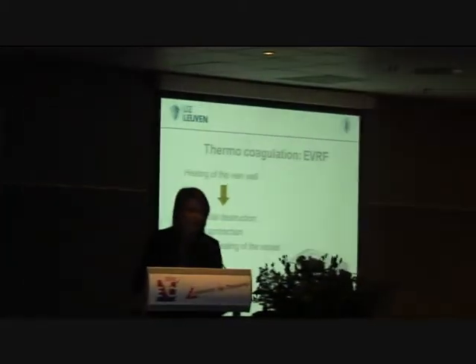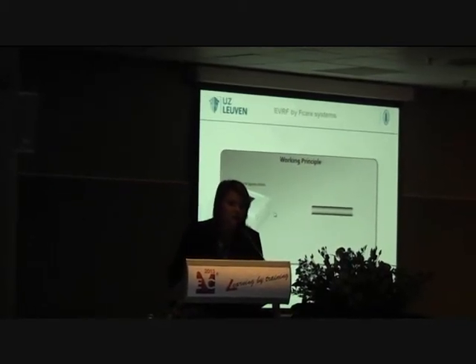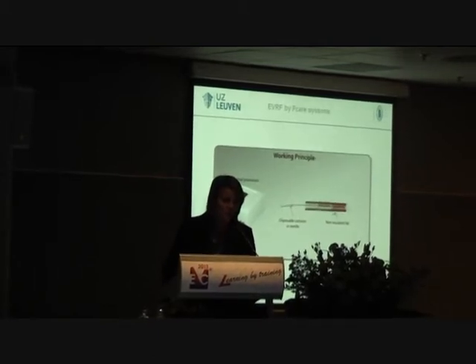It's the EVRF system. It's a type of thermocoagulation which works by heating up the vein wall, causing endothelial destruction. After the endothelial destruction, there will be a vein contraction and at the end a fibrotic sealing of the vessel. The working principle involves a generator connected to a disposable catheter or needle which has a non-insulated tip. This generates energy and the tip can be pulled back about 5 mm at a time.